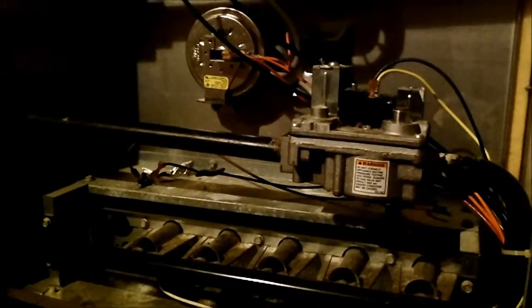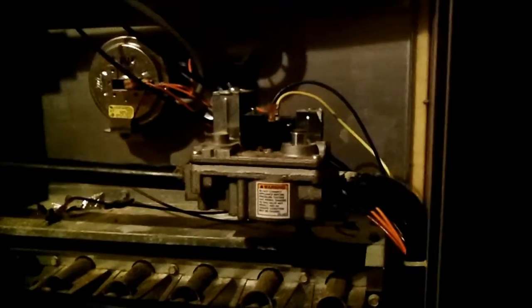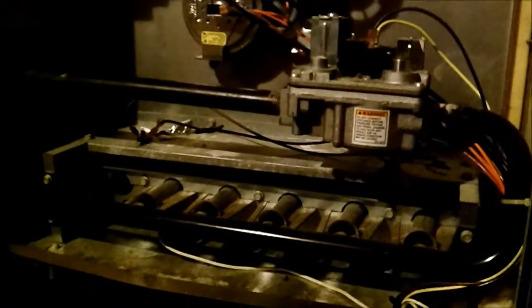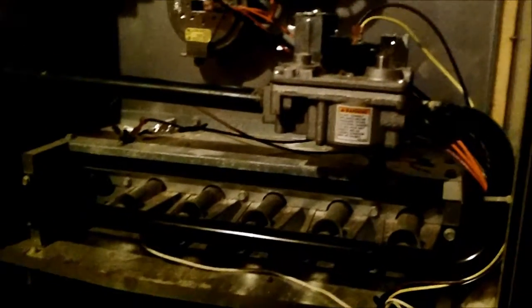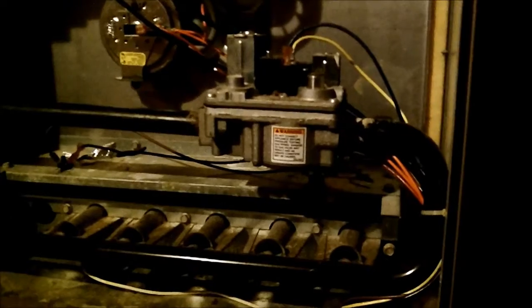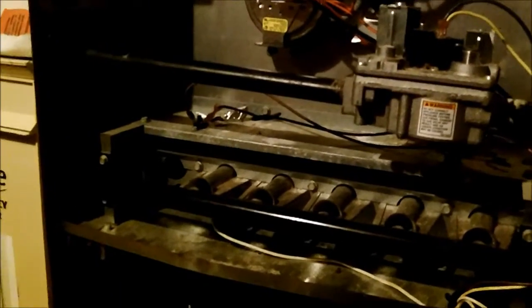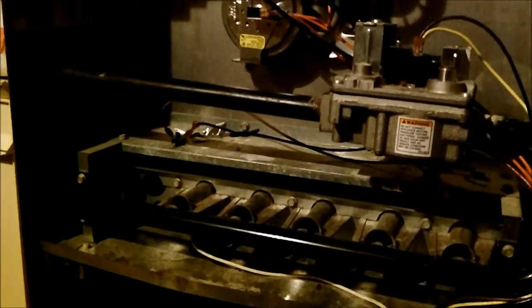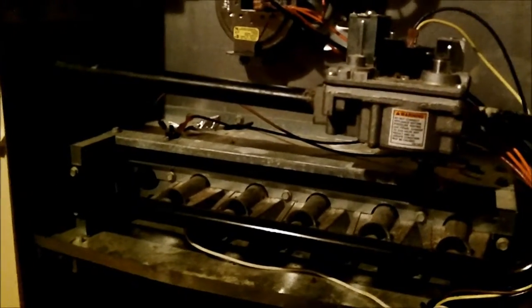They chose not to go with a steam humidifier due to cost. So today what we're going to be doing is adding a relay so that when the humidistat calls, and I'm using an EWC digital humidistat, when the humidistat says, hey, I need humidity, it's going to send a signal to a relay, which is in turn going to lock out the outdoor unit. I'm going to just run it to the G terminal on the circuit board, so it will turn on the fan and lock out the outdoor unit.